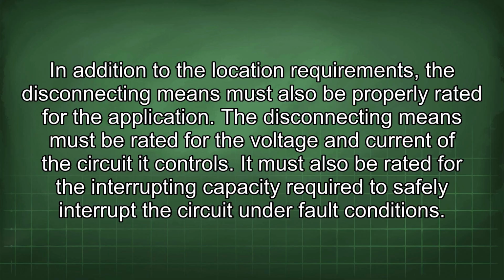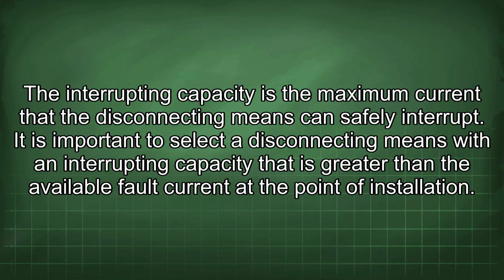The disconnecting means must be rated for the voltage and current of the circuit it controls. It must also be rated for the interrupting capacity required to safely interrupt the circuit under fault conditions. The interrupting capacity is the maximum current that the disconnecting means can safely interrupt. It is important to select a disconnecting means with an interrupting capacity that is greater than the available fault current at the point of installation.